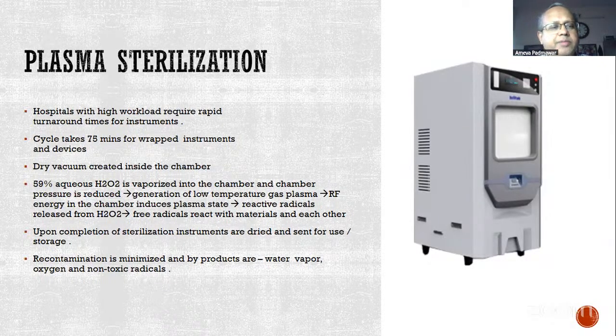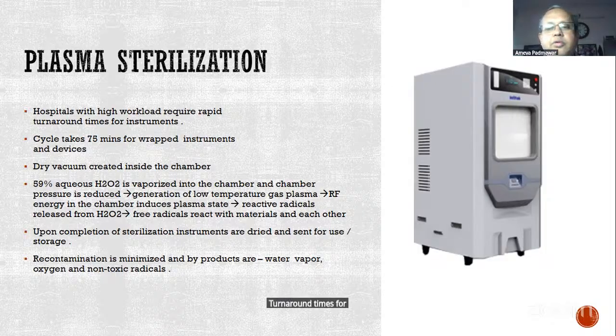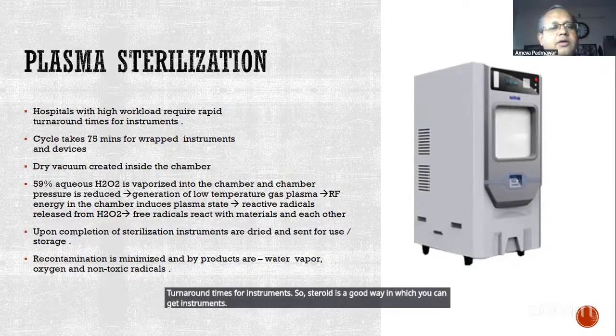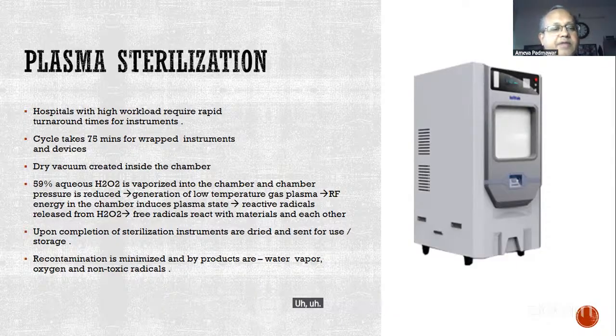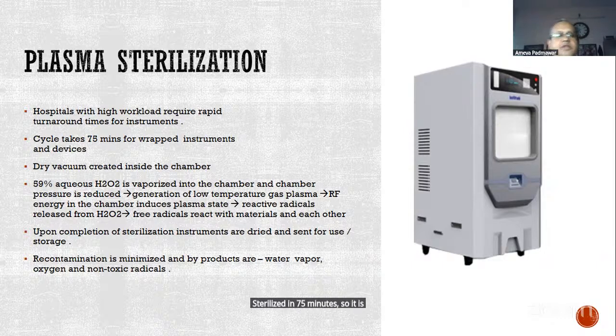Now, what is this plasma sterilization? Now, if you see in autoclaving, you're using high temperature, you're using thermal energy to get rid of all the live bugs. Here, you're using something known as the intermediate state of matter known as the plasma. Okay, so hospitals with high workload require rapid turnaround times for instruments. So, Sterrad is a good way in which you can get instruments sterilized in 75 minutes. So it is 1 hour, 15 minutes is the cycle.